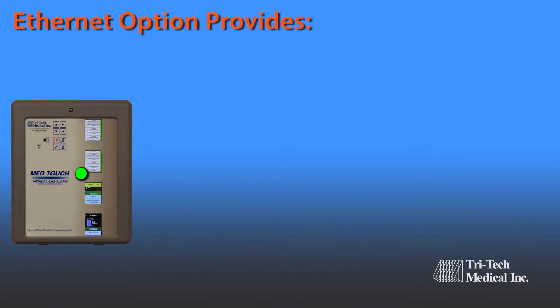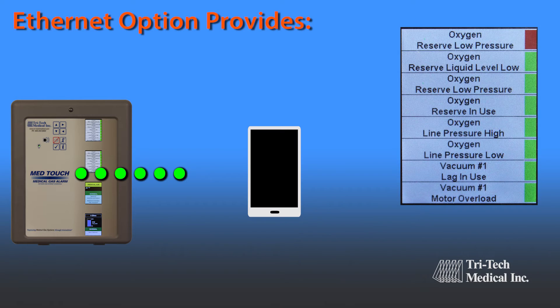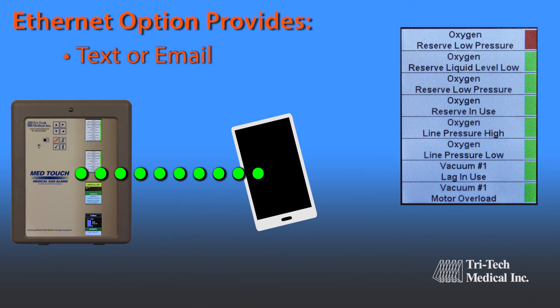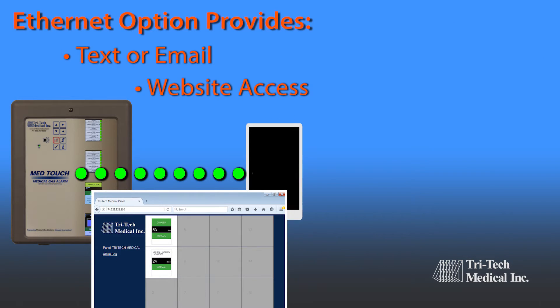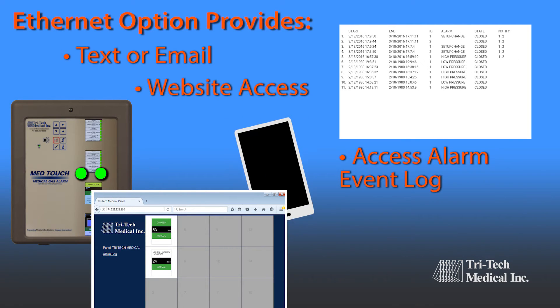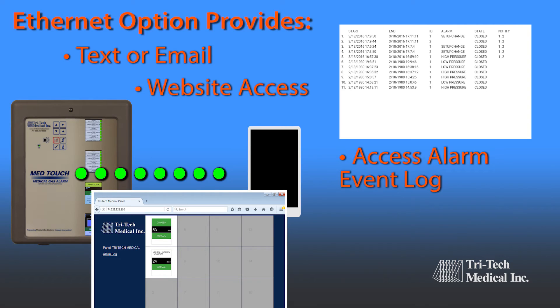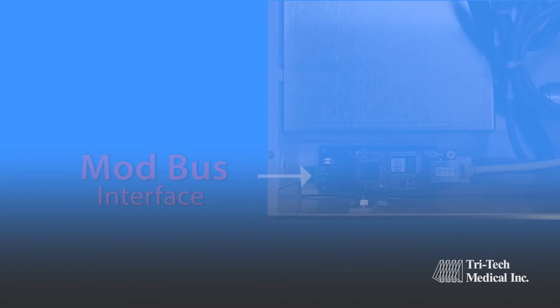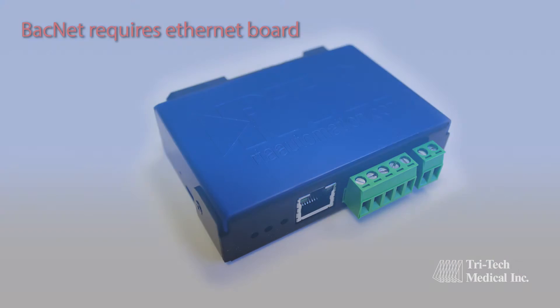Optional features include: the Ethernet option provides additional information directly to the user's mobile device, such as text or email notification of an alarm condition, website access to individual alarms to monitor current conditions, and access to the alarm event log. Also available are a Modbus interface for all Tri-Tech Medical MedTouch series alarms, and an optional BACnet interface.